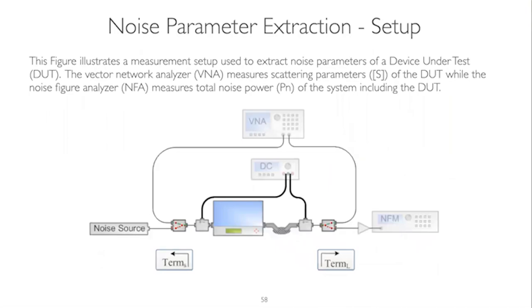So what does the setup look like? Basically you have a source tuner that's taking care of the impedance presented to the device. There are two major paths where we actually measure S-parameters of the device, and now we have a switching matrix that allows you to switch out the S-parameters to the noise path.